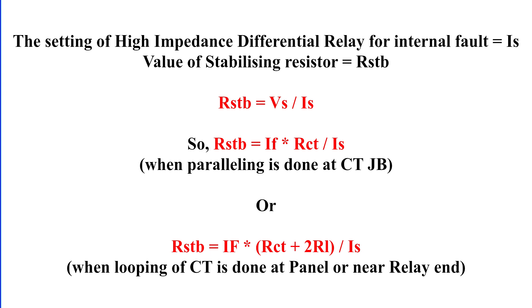Expanding it further, we get RSTB equals IF multiplied by RCT divided by IS when paralleling is done at CT junction box. Or RSTB equals IF multiplied by the sum of RCT and two times RL divided by IS when looping is done at the panel. This ensures that even under the worst case scenario of CT saturation, the current through the relay coil remains below the setting value, preventing false trips.